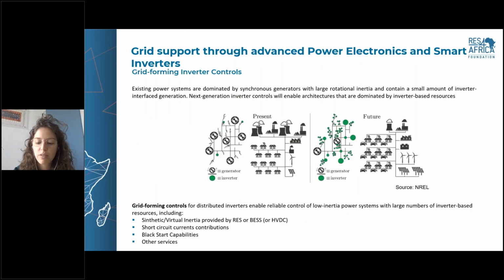It will also be important to improve control functions on inverters. Inverters will no longer only be passive users of the grid; new advanced functionalities will be needed, for example virtual inertia. In the past, synchronous generators connected to the grid intrinsically provided inertia, so if there was a power or frequency imbalance, they reacted instantaneously and brought the system back to equilibrium very fast. Virtual inertia control means the same: inverters that react to frequency imbalances, providing and regulating power output very quickly, which may also be enabled by battery energy storage systems.